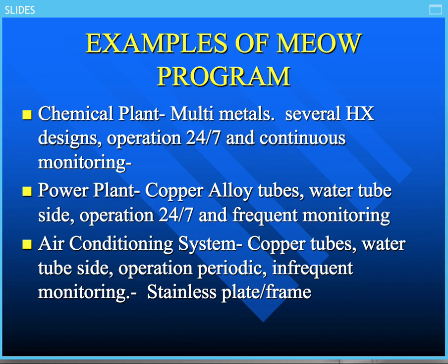But a chemical plant has multi-metals, several heat exchanger designs. That means water through the tubes, water through the shell, operates 24/7 in continuous monitoring. What type of thing do you have there? You have to have a good water treatment program to be able to cope with multi-metals in the system, and also the design of the heat exchangers, both for fouling potential and for continuous operation and scaling tendency and corrosion. And you should have continuous monitoring in a chemical plant so that you minimize that. That goes true for refineries as well as chemical plants.